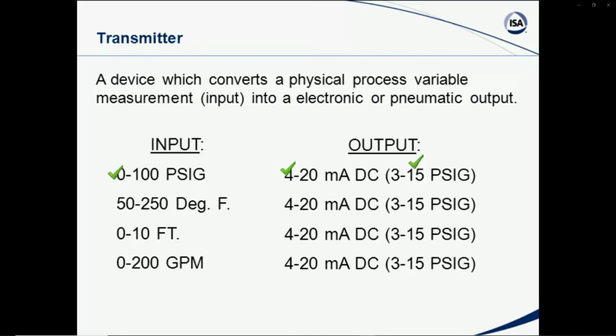But in any event, this intelligence, we do need to get that and be able to apply that intelligence to our control system. It could be a temperature, 50 to 250 degrees Fahrenheit. It could be a level, feet or inches of level that we have in a tank, a vessel, or storage unit, or it could be flow rate, 0 to 200 gallons per minute, some volumetric flow rate that we have interest in. But what we're doing is getting these into a common output, if you will, from our sensor, from our transmitter. And I will talk a lot using the term 4 to 20 milliamp, 24 volt DC for our electronic units that we're using for transmitters.